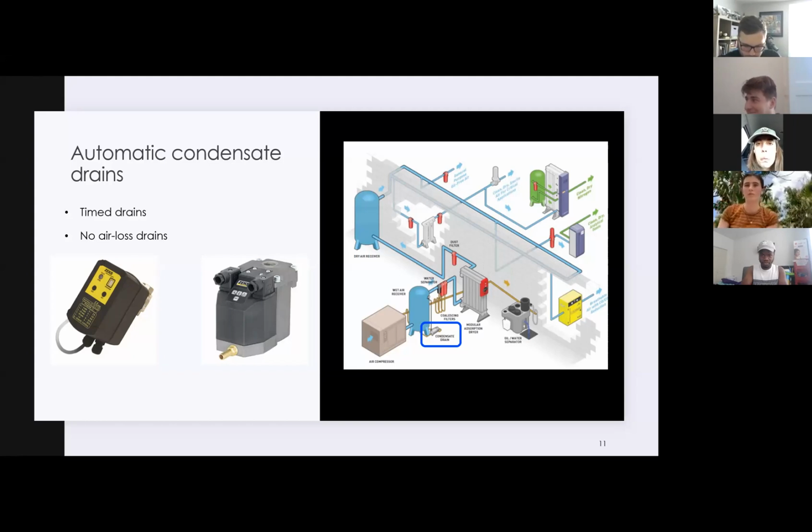My hunch would be, first thing, I would tell them you're destroying your piping system and all your process equipment, causing tons of undue harm, totally separate from energy cost savings. We've got to help you with that. But then the second one is the maintenance staff probably have opened up a bunch of valves and have a whole bunch of bleeders all over the place, I bet, because they probably do get condensate accumulating. And so that wasted compressed air does show up back at the compressor in terms of excess energy usage because they're just venting it.